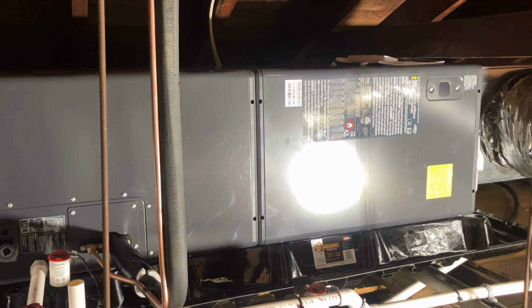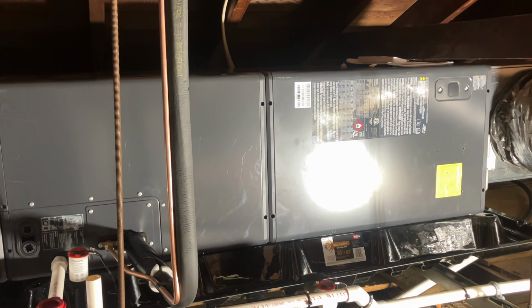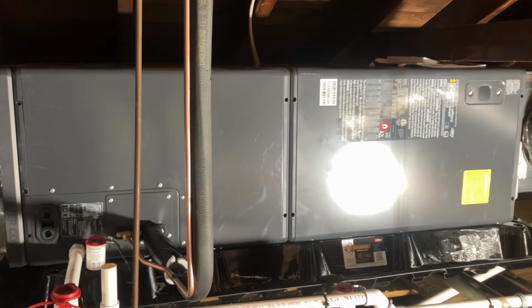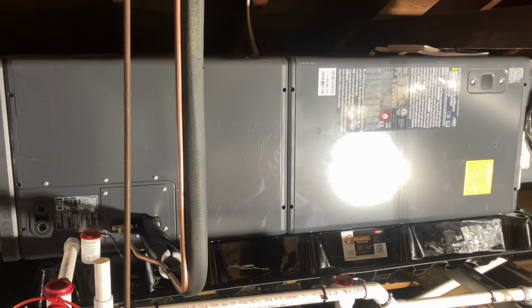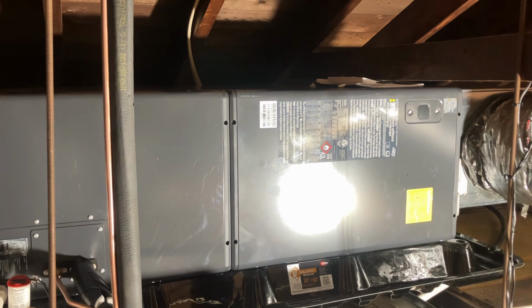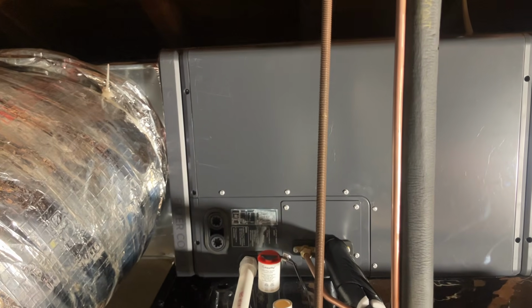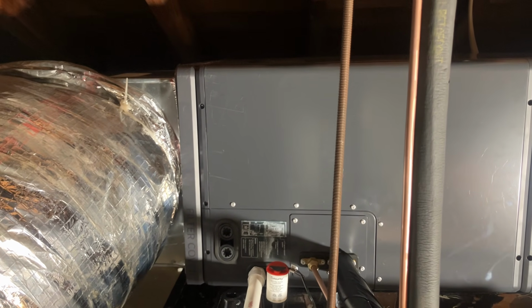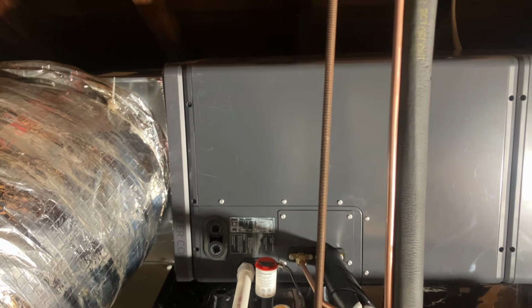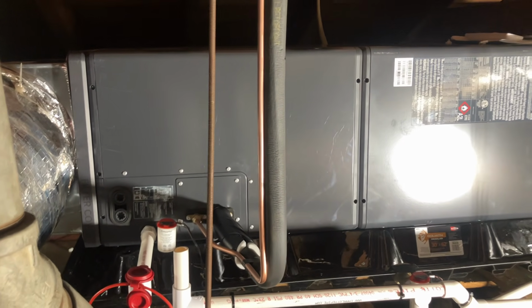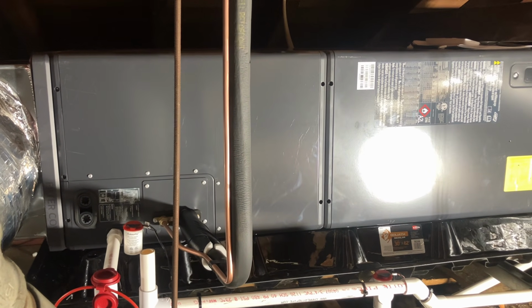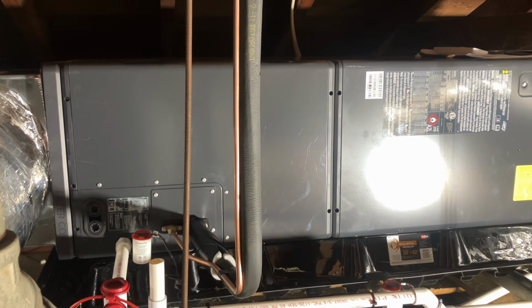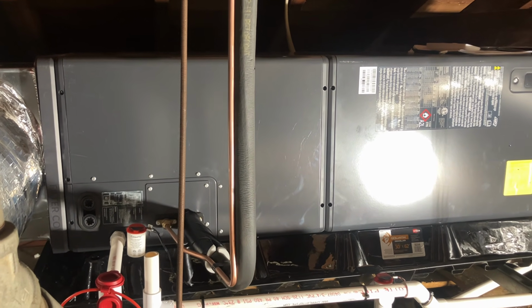This is the PAH 36,000 BTU air handler. It communicates with the thermostat via 2-wire serial communication, and it's installed here in a horizontal configuration. One of the great advantages of the PAH air handlers on the Extreme 2 is the multi-positional evaporator coil—horizontal, upflow, downflow, left to right—so whether your application requires any of that, you're good. Like an attic installation or a closet, downflow or upflow, we have it.